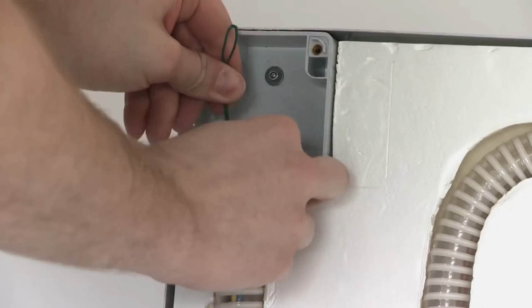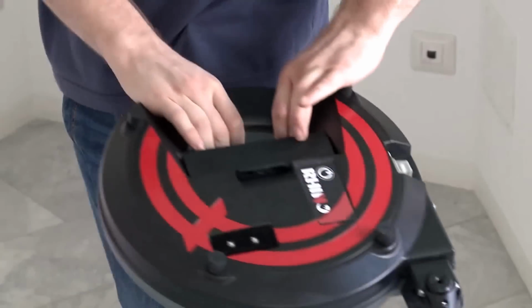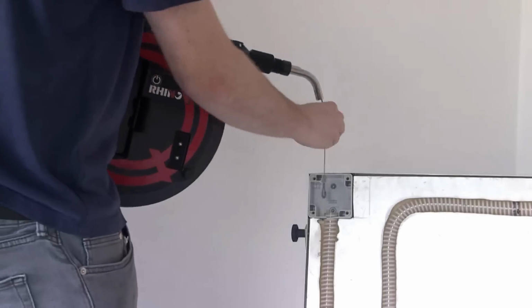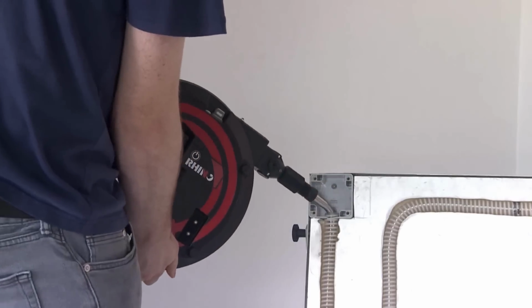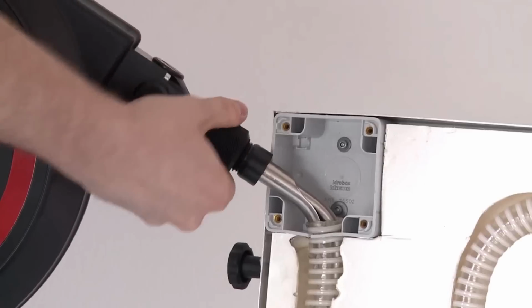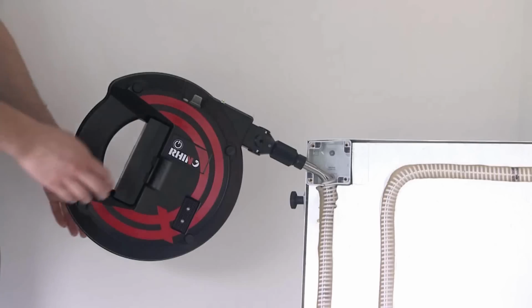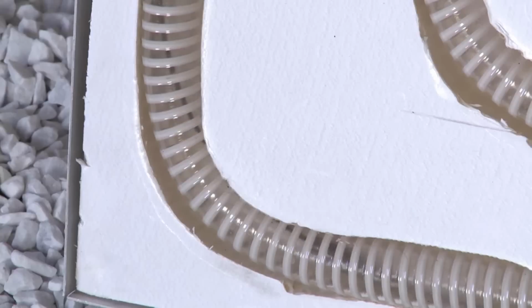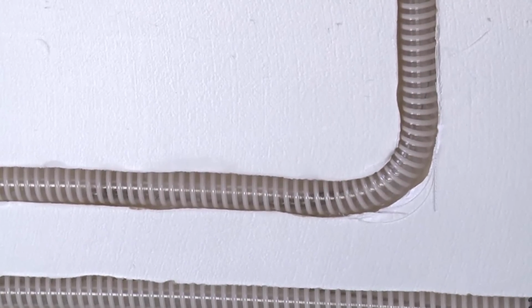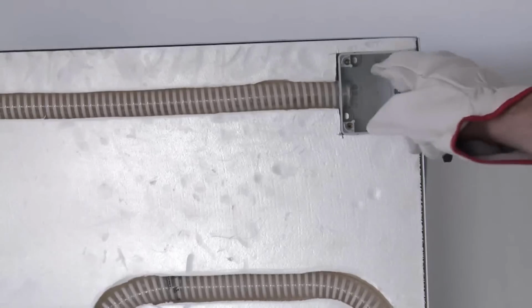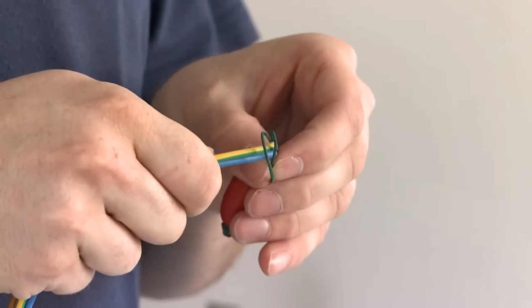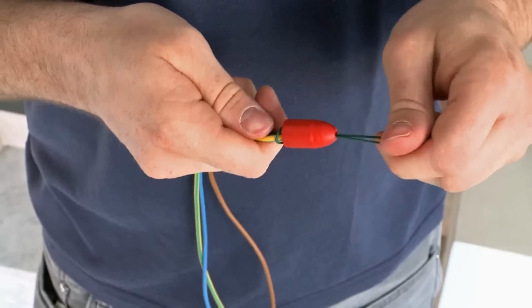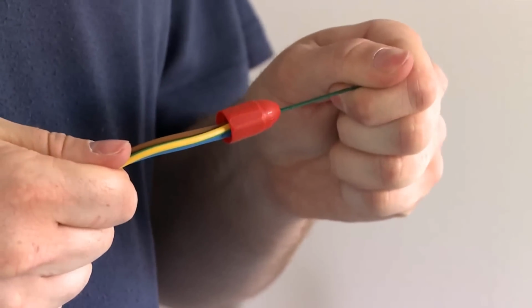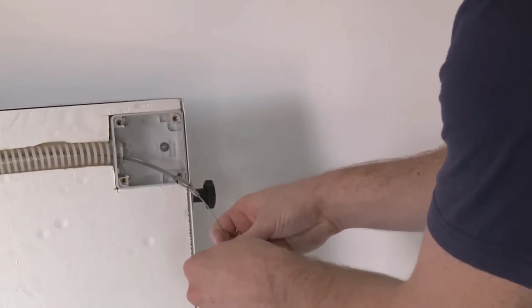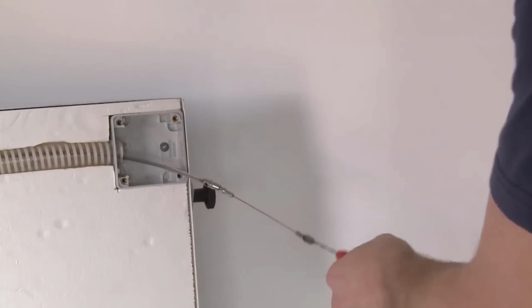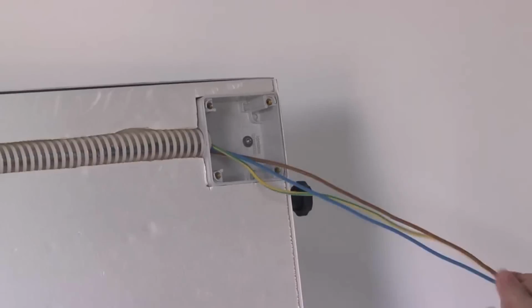To use the Rhino Cable Pulling Probe, you first insert the pointed end into the conduit or pipe where you want to run the cable. Then you attach the cable to the back end of the probe and use it to pull the cable through the conduit or pipe. The flexible nature of the probe allows it to navigate bends and turns in the conduit, making it easier to pull the cable through. It is an essential tool for electricians and other professionals who need to run cables through tight or hard-to-reach spaces. It can save time and effort compared to running cables by hand, and it can also help minimize the risk of damage to the cables or the conduit.